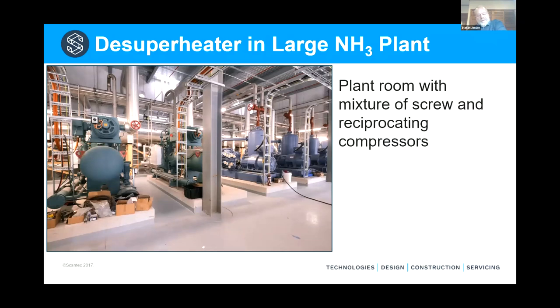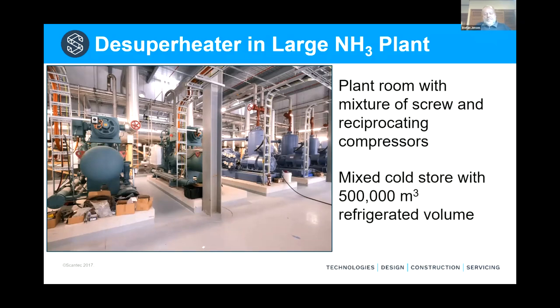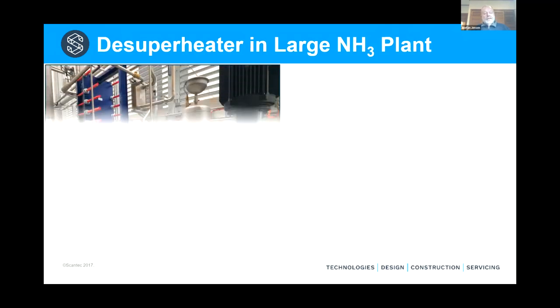Then we come to this, a bespoke ammonia plant that runs a 500,000 cubic meter cold store in Queensland. So we have a mixture of compressors here. On the left, you can see some screw compressors, and on the right, you see some reciprocators. We are recovering heat from the reciprocating compressors. They sit on the second compression stage. Screw compressors sit on the first compression stage.